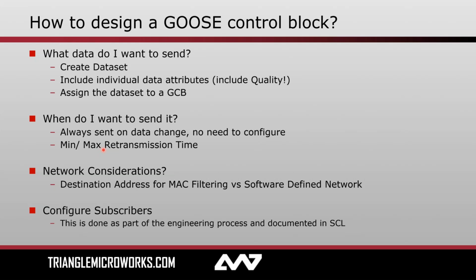Next, network considerations. So are my devices at risk of overloading because of too much sample values traffic or too much GOOSE traffic? This was, I would say, a more common problem in the early days of 61850. Today, this really just depends on you and your application. If you've got a tremendous amount of sample values, then it's something that you might want to take into consideration. If you're working on a smaller system with just GOOSE, you might not have a problem. But yeah, these are things that you want to keep in mind.